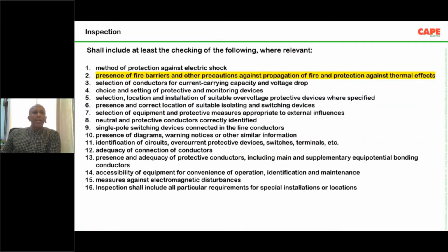The testing the standard recommends we call verification. It consists of inspection and testing. Inspection means we have to inspect a site, check the drawings, and find out what the concepts are. Number one, the method of protection against electric shock: what is the basic concept adopted in a building in order to stop shock hazard? The second one, presence of fire barriers and other precautions against propagation of fire and protection against thermal effects. This is very important, especially for fire protection.